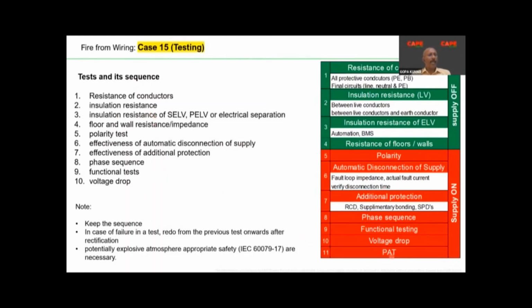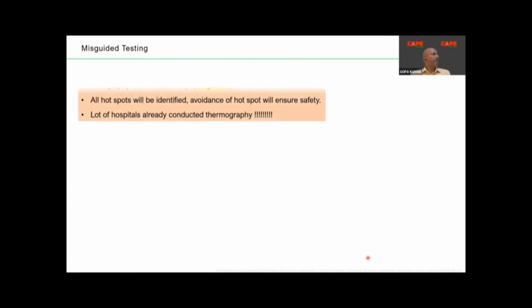And the last one, PAT. PAT stands for Portable Appliance Test. In Europe and America, or for example in Australia, this has also been made a mandatory thing. There is a PAT test instrument available. If you buy some kind of equipment and you want to connect it to your electrical wiring, because your wiring is very safe, now that the equipment is connected, you must do a PAT quite frequently.